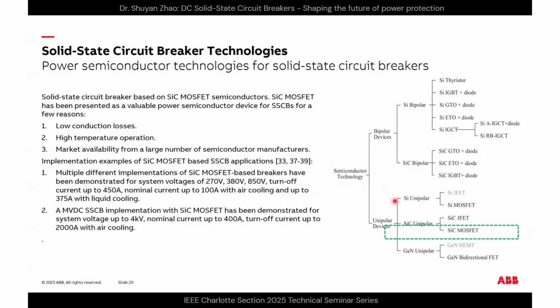Multiple different implementations of SiC MOSFET-based breakers have been demonstrated for different system voltages from 270 volts up to 850 volts or even higher, with turn-off current up to 450 amps, nominal current up to 100 amps, using passive cooling, air cooling, or liquid cooling. Different cooling technologies are also under development right now.